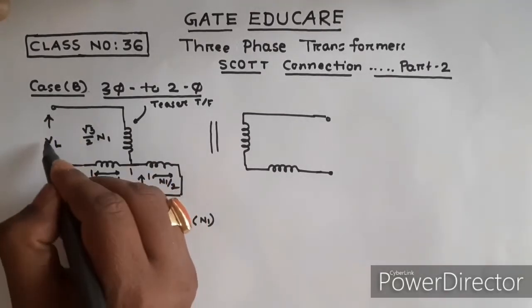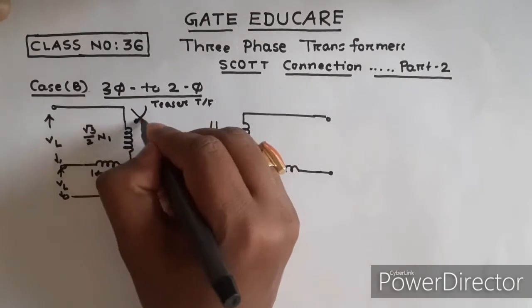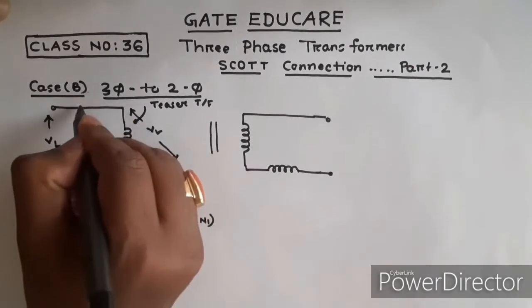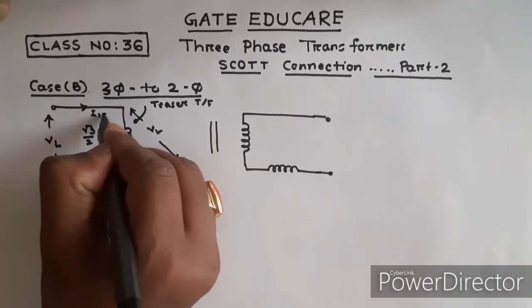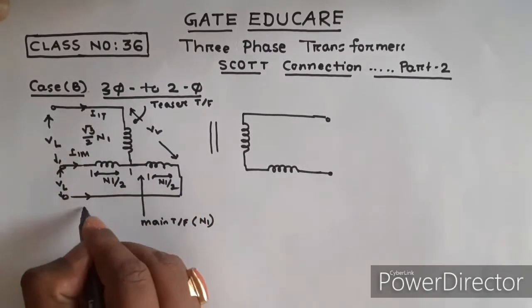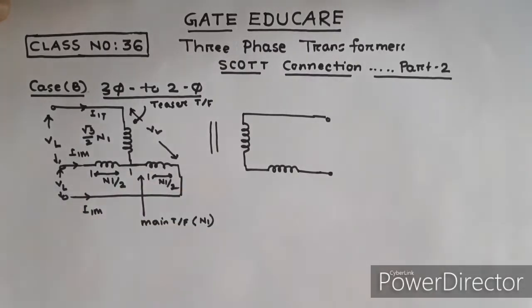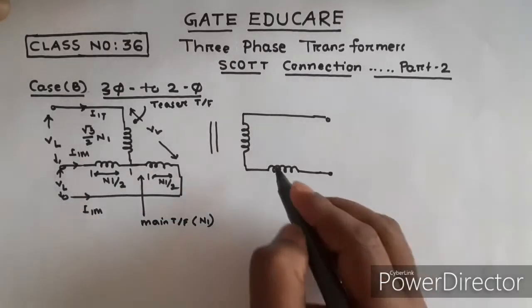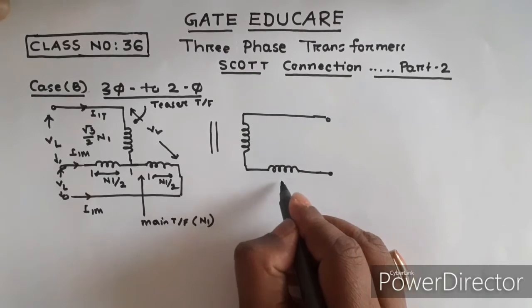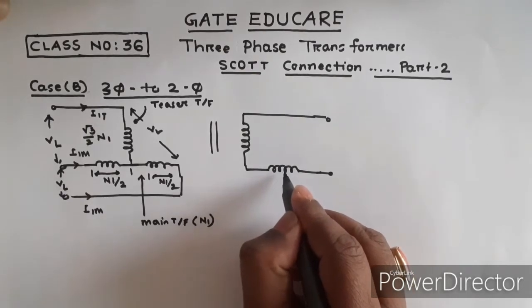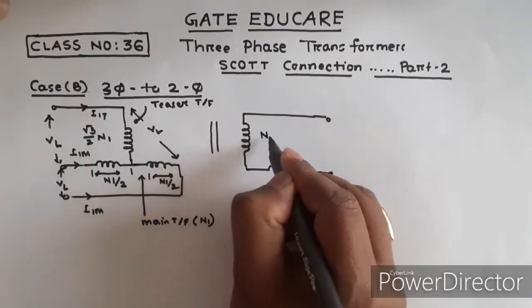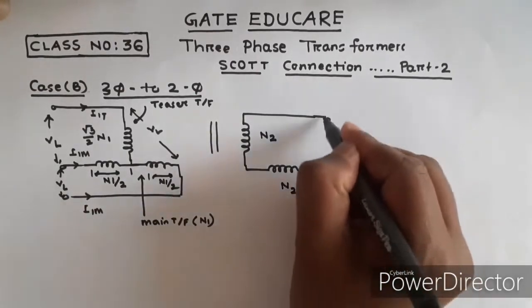Let VL be the line voltage. The teaser transformer primary current is I1T and the main transformer primary current is I1M. The secondary of the main transformer is not center-tapped. If the secondary of the main transformer has N2 number of turns, then the secondary of the teaser transformer must also be N2 number of turns to get a balanced output.